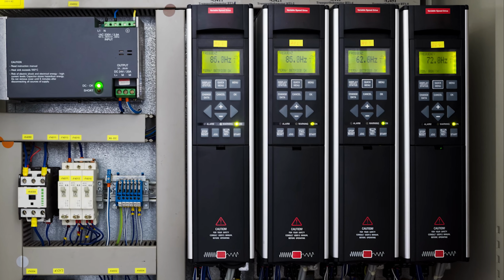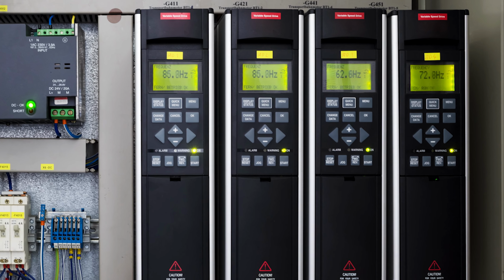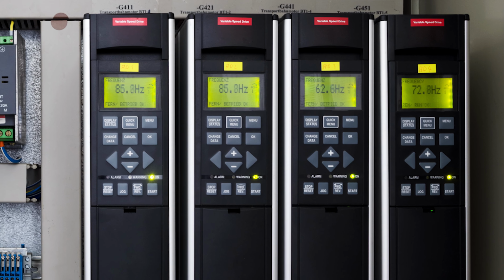These work by electronically manipulating the frequency of the power supplied to the motor. As we saw before, a motor's speed is directly related to the frequency of the AC. A VSD intercepts the power supply and converts it to a higher or lower frequency to change the motor's speed according to demand.